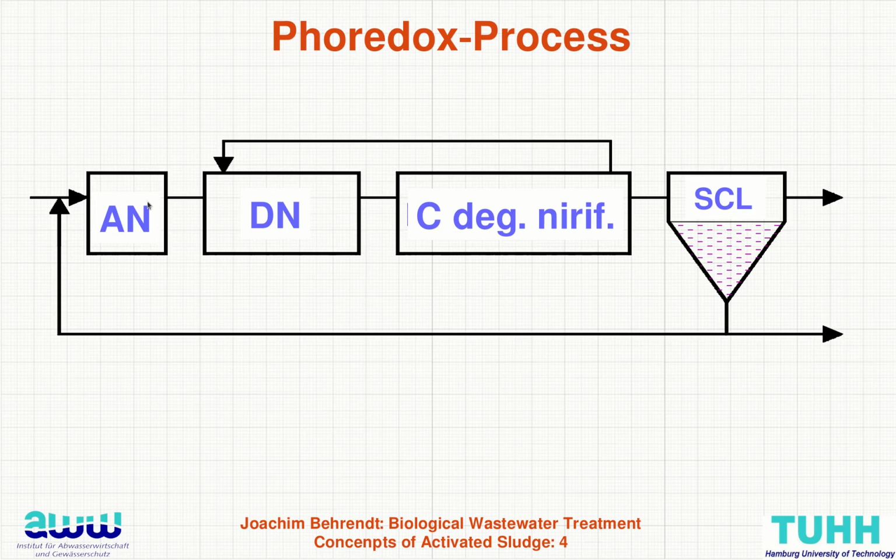There are enough basins available, and so if you redirect the recirculation a little bit later and have an anoxic zone beforehand, this is easy to implement. And finally, if you need more place for denitrification, you can skip the anaerobic part easily and add some flocculants.